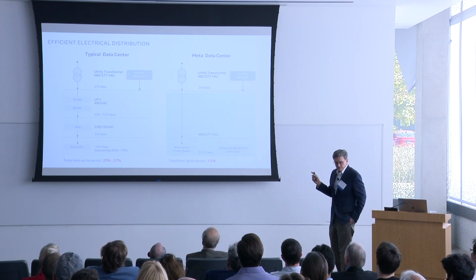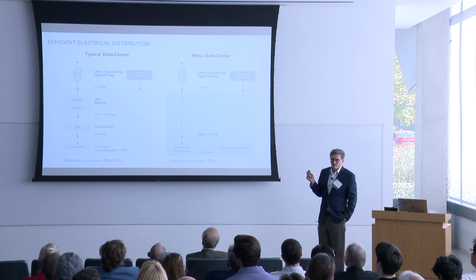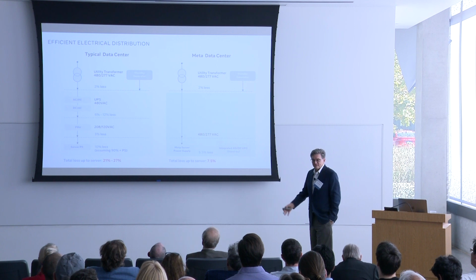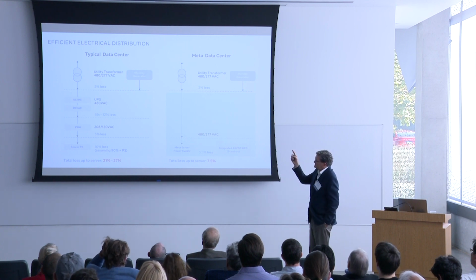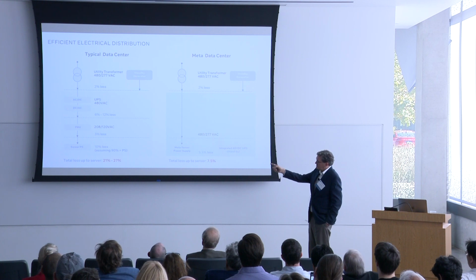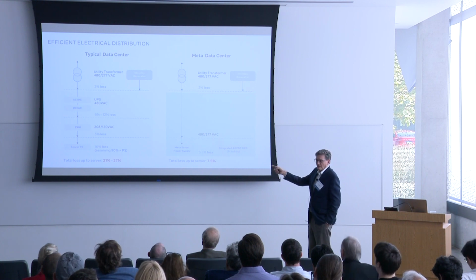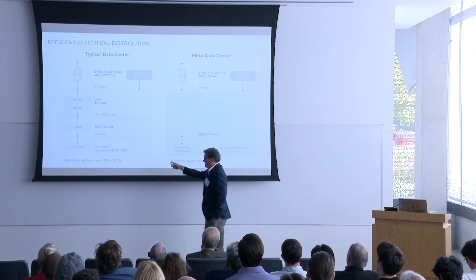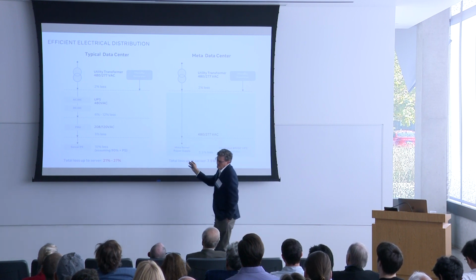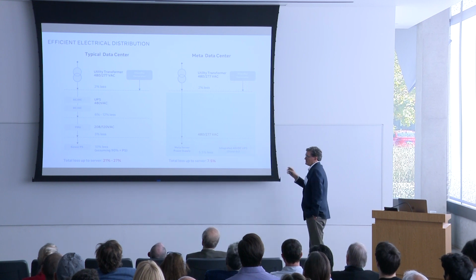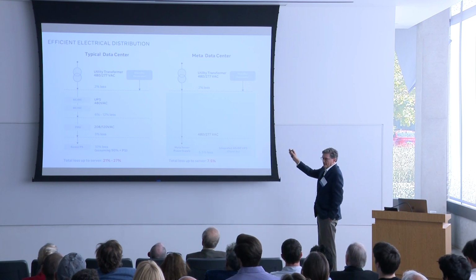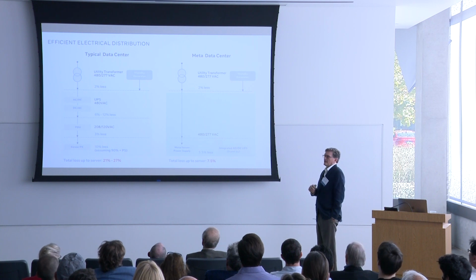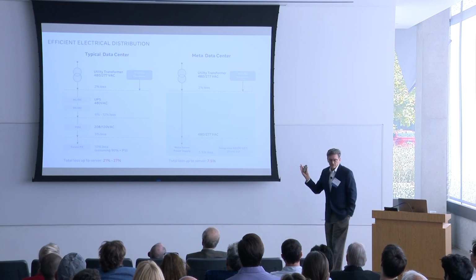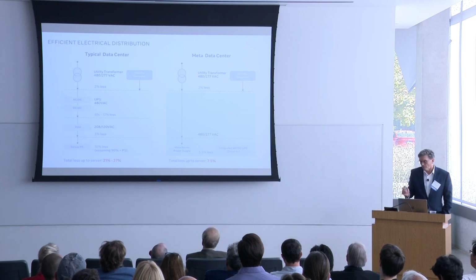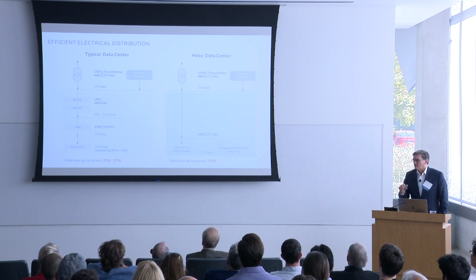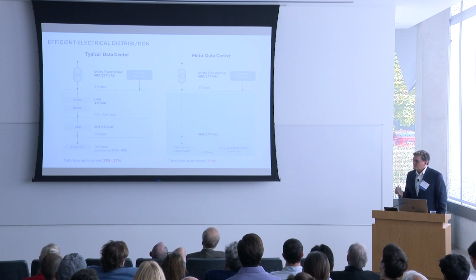First is the power distribution, and I would say this is mostly a solved problem if you control your whole stack. On the left is how you get power from the grid down to your server. If you don't build your own stuff and you go to a colo, your losses might be in this range, maybe 10% if you're really paying attention, could be higher. If you can design the whole stack, you minimize the number of transformations and you gain some efficiency right off the bat. This is what we've been doing for a decade or more, and we get incremental performance improvements over time, but mostly on the server side at this point.